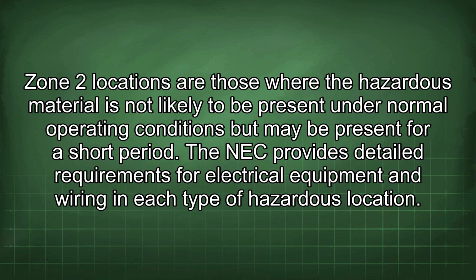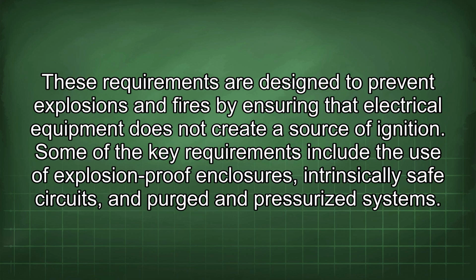The NEC provides detailed requirements for electrical equipment and wiring in each type of hazardous location. These requirements are designed to prevent explosions and fires by ensuring that electrical equipment does not create a source of ignition. Some of the key requirements include the use of explosion-proof enclosures, intrinsically safe circuits, and purged and pressurized systems.